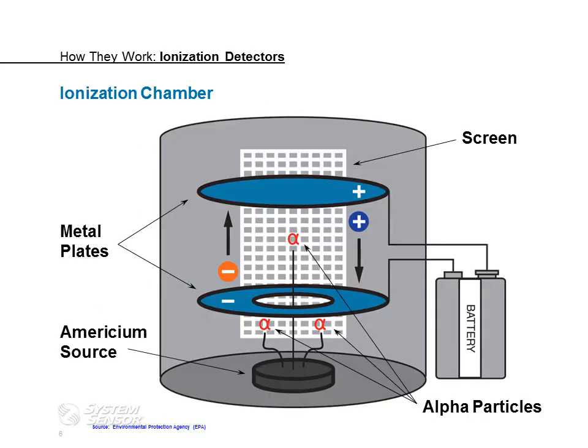The second type of detector that's available is an ionization detector. An ionization detector uses a radioactive material, americium-241, as a source, and it's looking for smoke particles to enter its sensing chamber. They bond and change the charge of the ions, which changes your current draw, your current consumption, which gives you your alarm. Ionization detectors do have a place, and they are a valuable product. Unfortunately, a lot of times they are misapplied and misused. They're really designed for locations that are going to have hot flash fires versus a standard commercial application where you're going to have a colder smoldering fire.